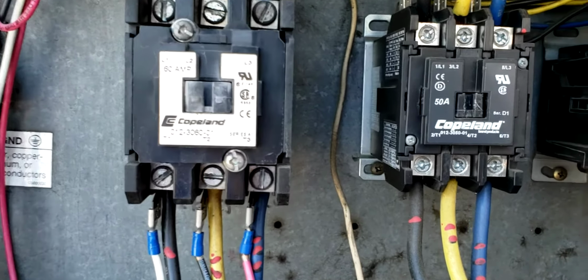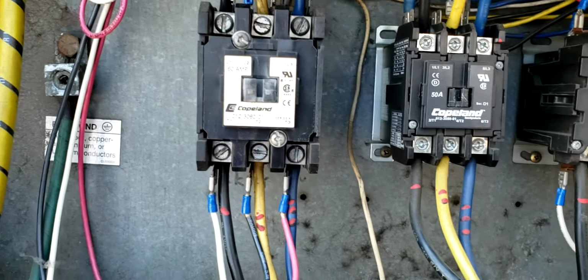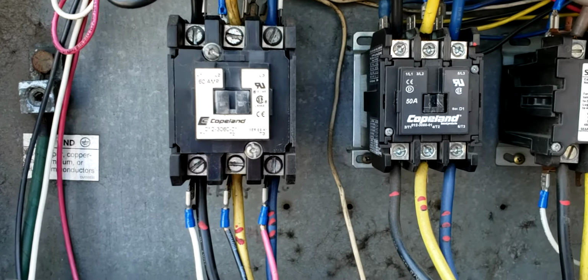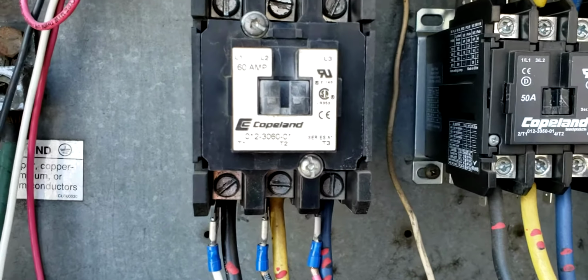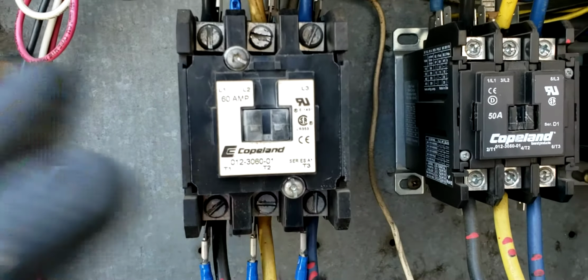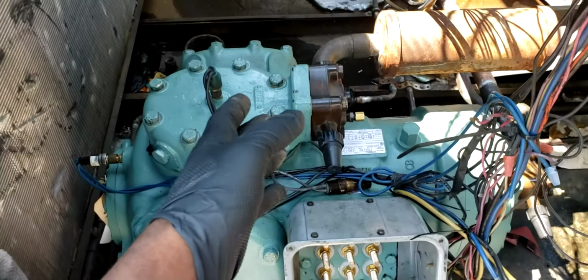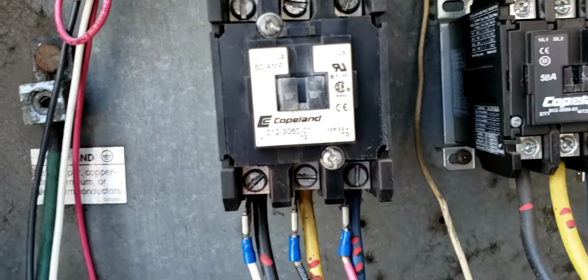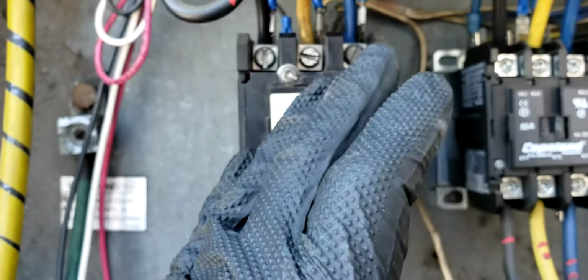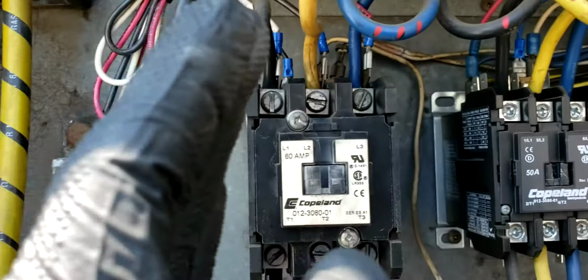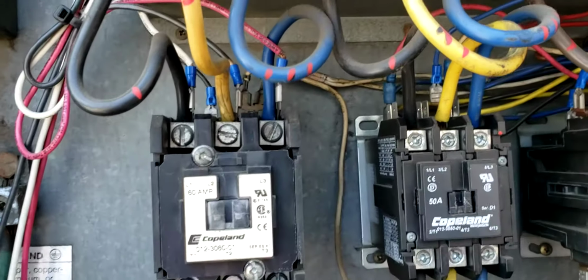That will never work, because now the windings are going to have different rotation inside of the compressor. So it has to be the same rotation. The rotation on this compressor doesn't really matter unless you're doing part winding, whereas both contactor 1, or C1, and contactor number 2, or C2, have to have the same phase when it comes to the input power. And so let's get back down here now.